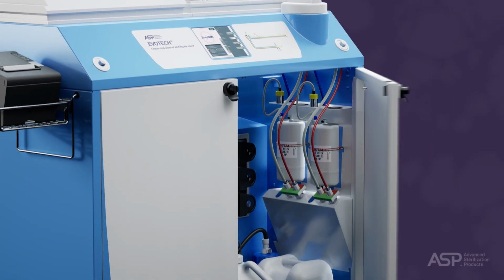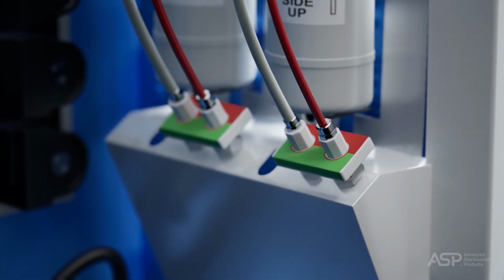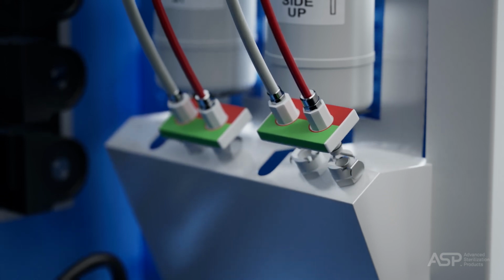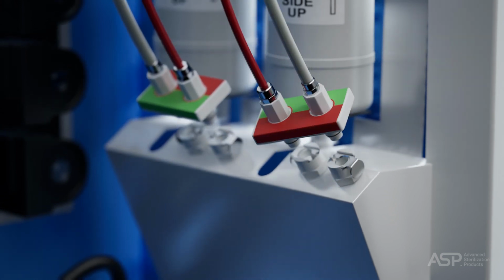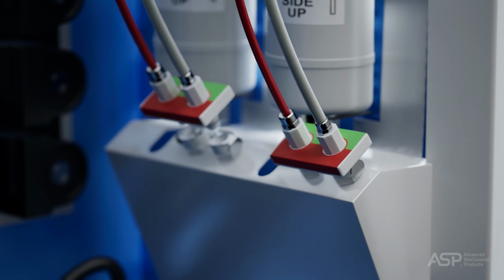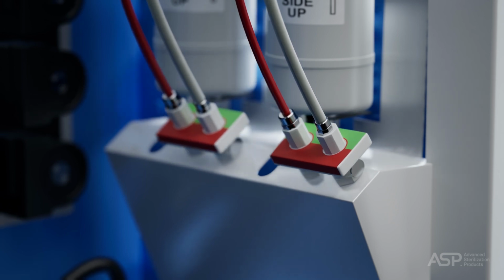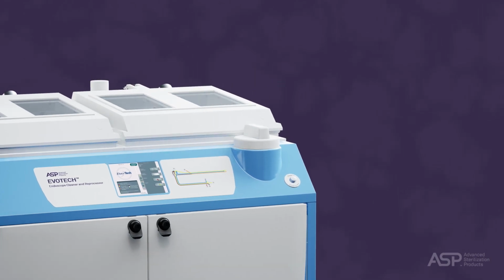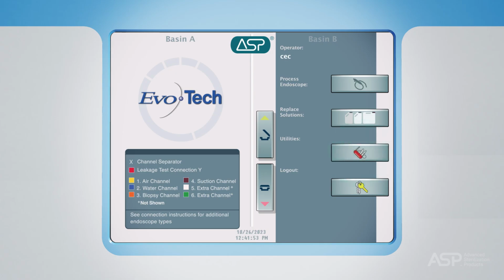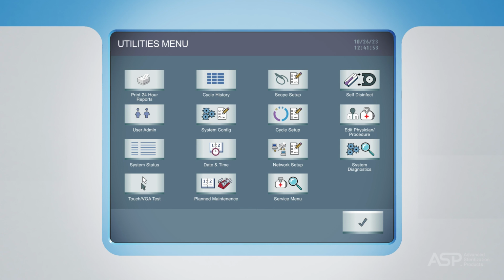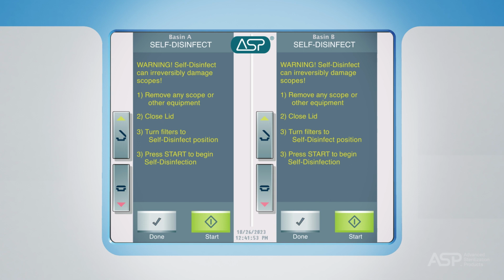Open the right-hand door of the system and unsnap the quick disconnect fitting on the 0.2 micron filter bracket. Rotate it 180 degrees and snap it firmly back into place. You will hear the fitting click into place when properly seated. The red label on the filter connector should be facing left. Next, close both lids. Then go into your utility screen and select the Self-disinfect icon located on the top right of the screen.